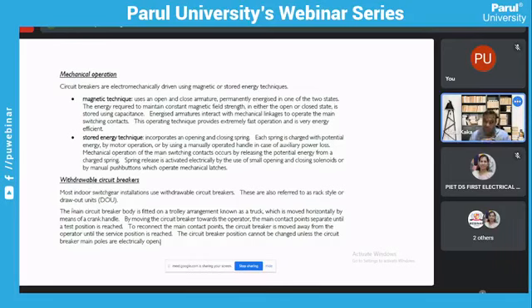So the basic design of the switchgear is that whenever you make any closing as well as opening operation, it straight away triggers to charge the spring again so that any further operations can be catered to by the breaker. But even if there is a loss of auxiliary power, you can still do that by an external handle which is provided as a loose accessory by the vendors. Also, the mechanical operation for the main switching contacts occurs by releasing the potential energy from the charged spring. So that is the point I was trying to make here. Spring release is activated electrically by small opening and closing solenoids or by a manual push button. So there are push buttons as well as TNC switches which are given there, so you can easily release it, and that's activated by using a small opening and closing coil.